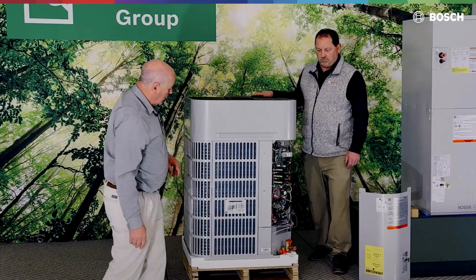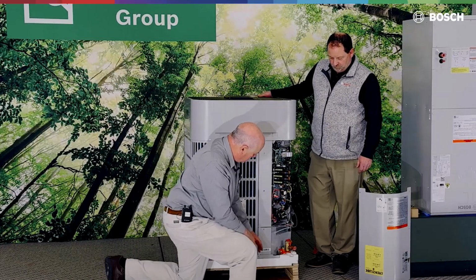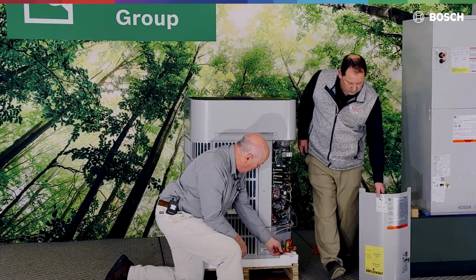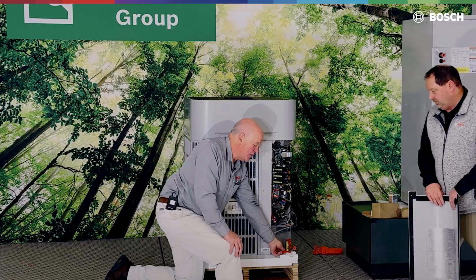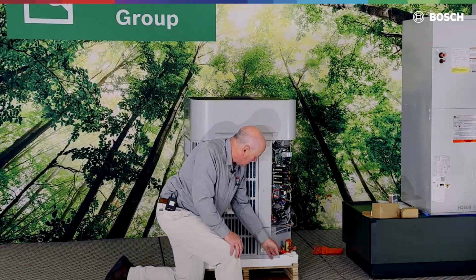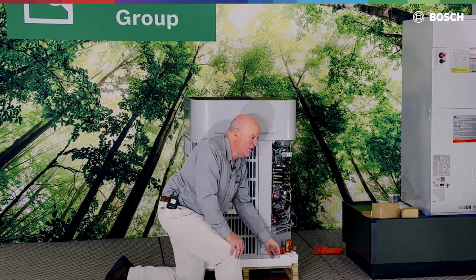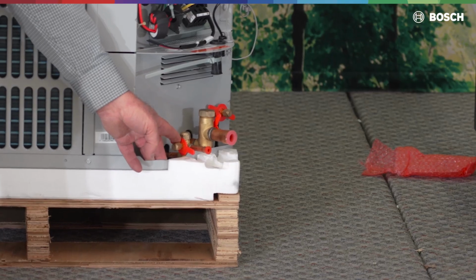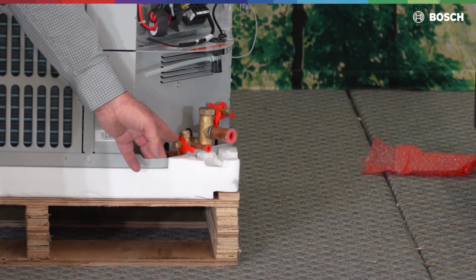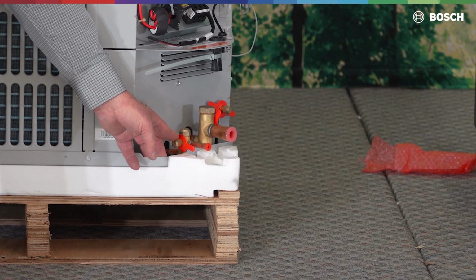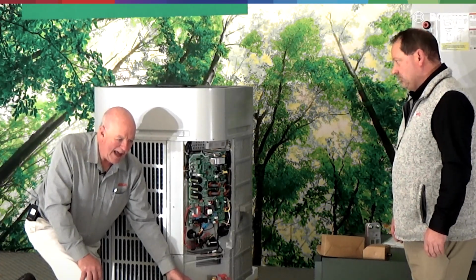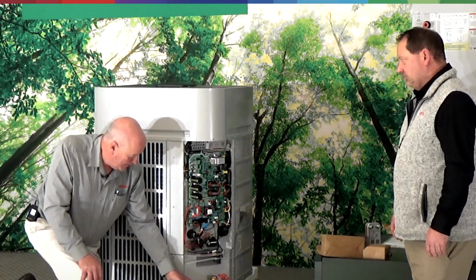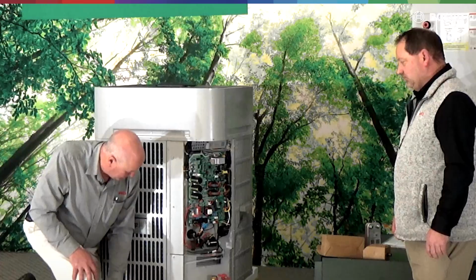One of the things that Chris talked about earlier today, how do we know this is a 454B? There are red plastic indicators on our fittings. These are supposed to remain on there at all times. Do not take them off when you do the install. This is to alert a contractor that this is not R410A, this is R454B. Do not accidentally place the wrong refrigerant in this application of this unit.